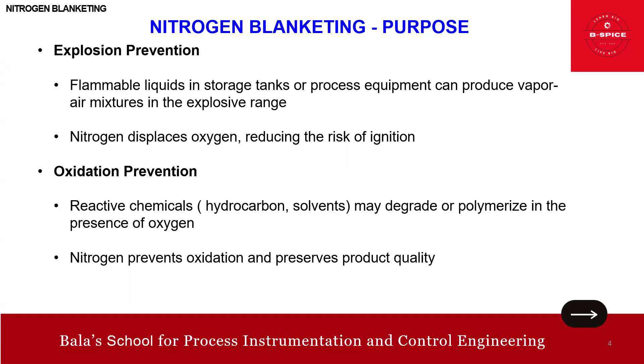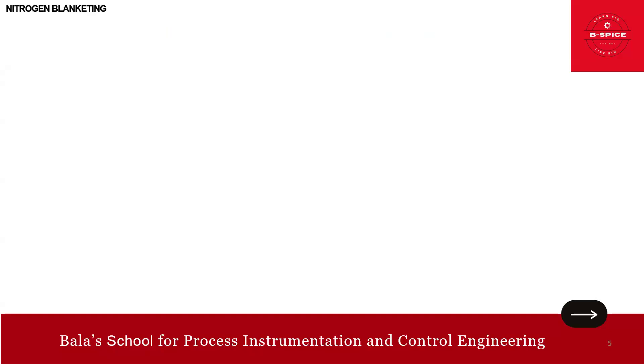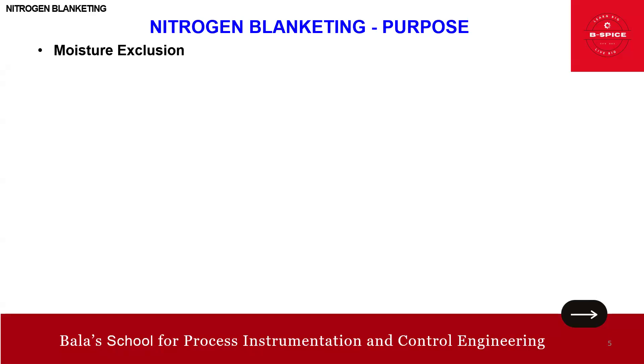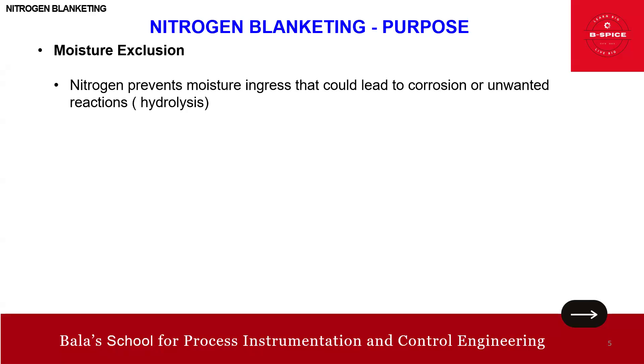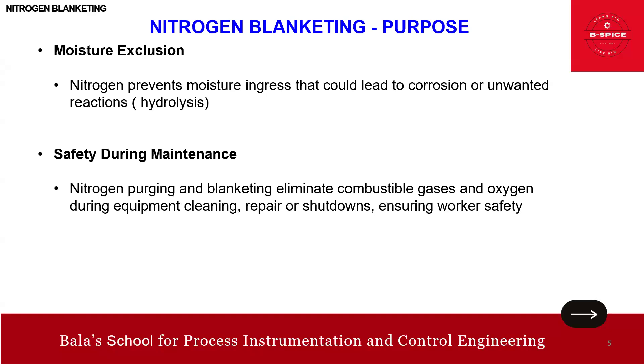The third purpose is moisture exclusion — nitrogen prevents moisture ingress that could lead to corrosion or unwanted reactions such as hydrolysis. The fourth purpose is safety during maintenance: nitrogen purging and blanketing eliminate combustible gases and oxygen during equipment cleaning, repair, or shutdowns, ensuring worker safety.